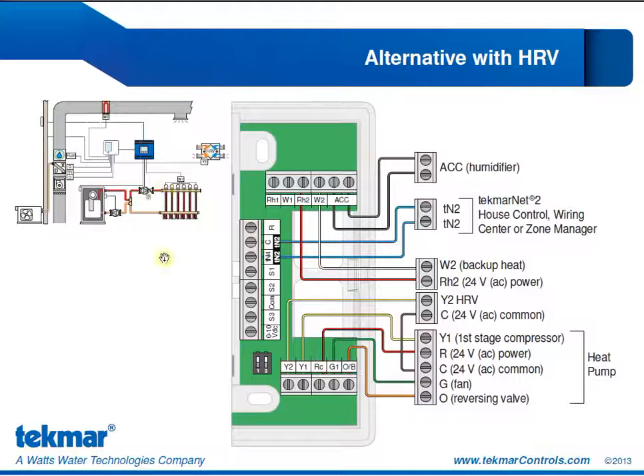Let's look at the wiring. We see those TN2 connections to a house control for the radiant operation. So the house control will be controlling the valves and the pump for the radiant. Our second stage of heat is at our heat pump. We have the Y1 connection only. So R comes in from our heat pump and is going to the Y1. We have the fan, obviously, and O for the reversing valve to switch into cooling mode.